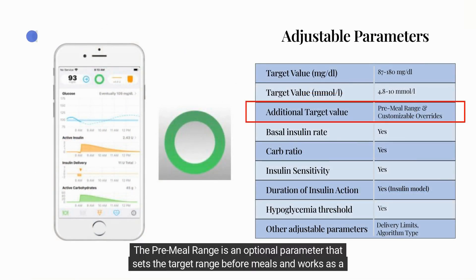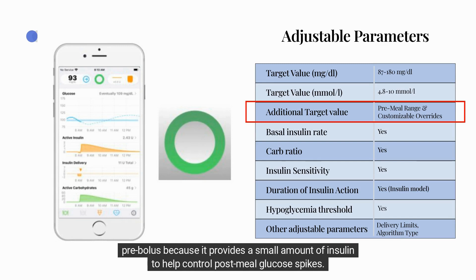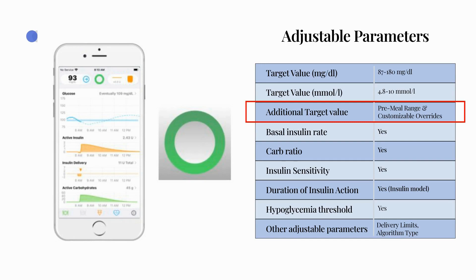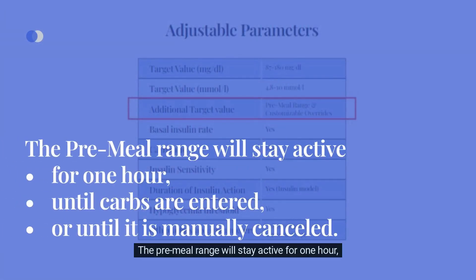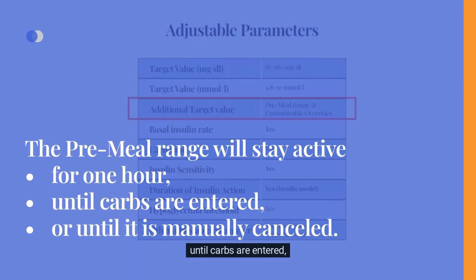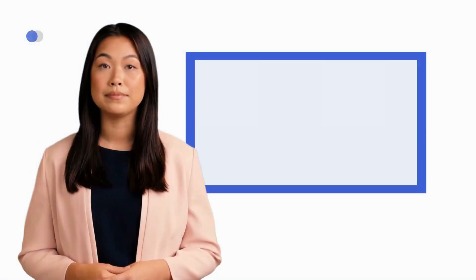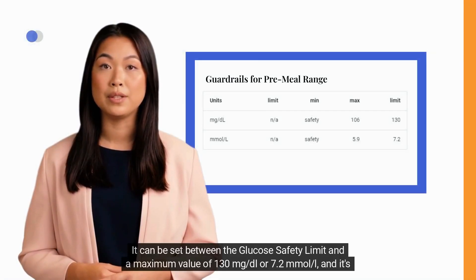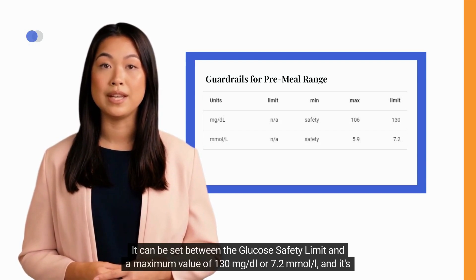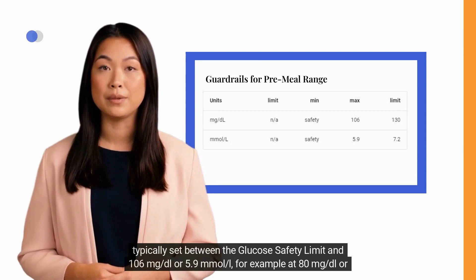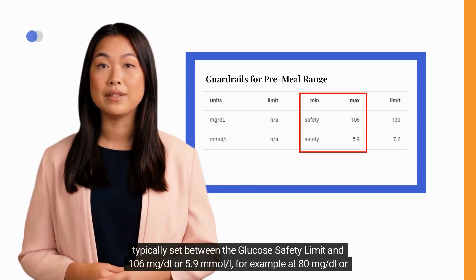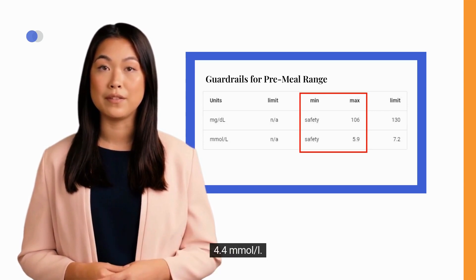The pre-meal range is an optional parameter that sets the target range before meals, acting as a pre-bolus by providing a small amount of insulin to help control post-meal glucose spikes. It stays active for one hour, until carbs are entered, or until it is manually cancelled — whichever comes first. It can be set between the glucose safety limit and a maximum of 130 mg/dL or 7.2 mmol/L, typically set around 80 mg/dL or 4.4 mmol/L.